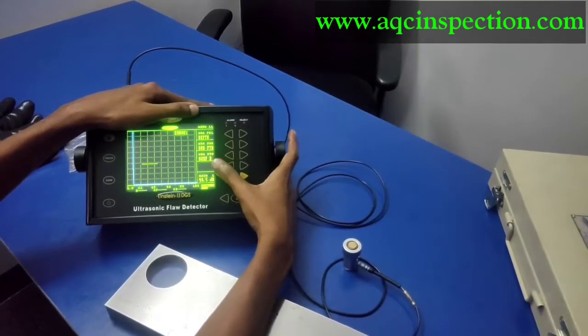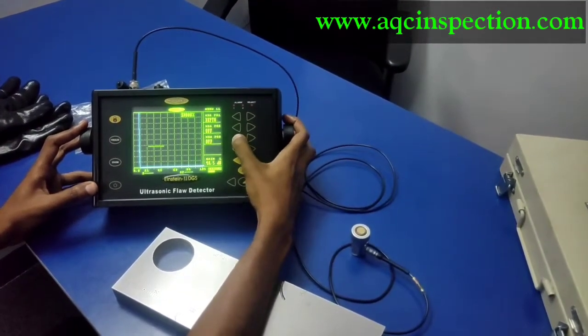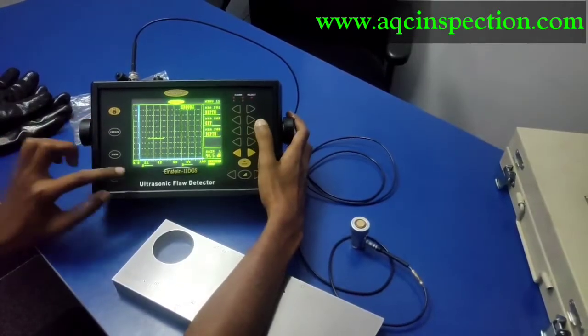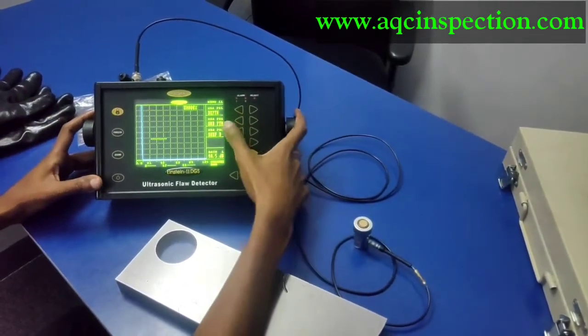When you are using an angle probe, you can use this. Using a normal probe, you don't want this, you can switch it off since we are going to see only the depth here. If you are going to use angle probe, this is a must.